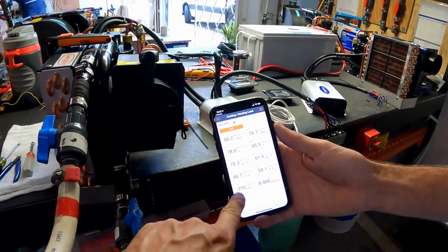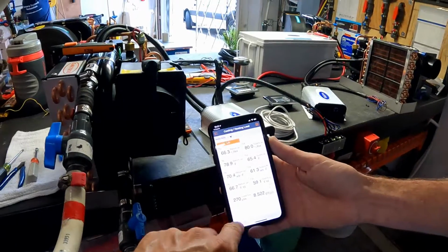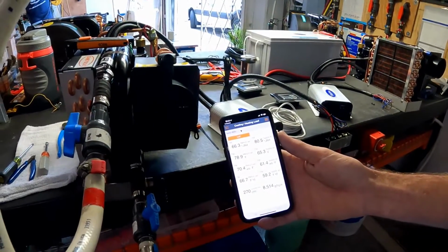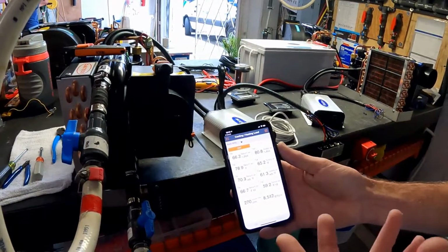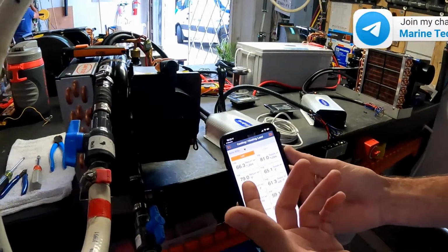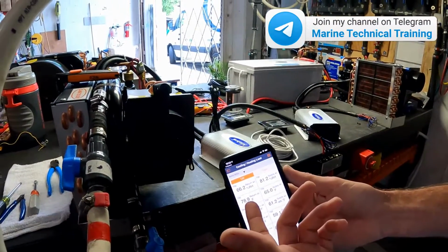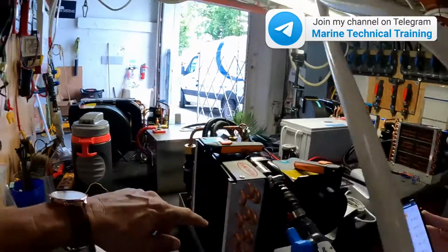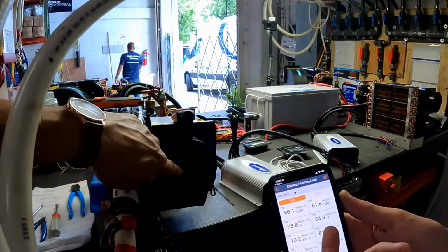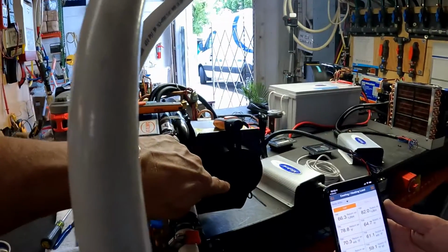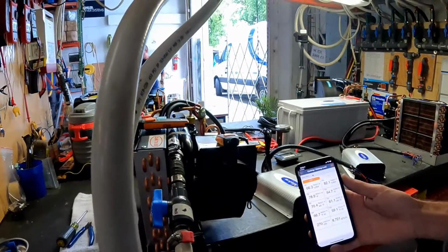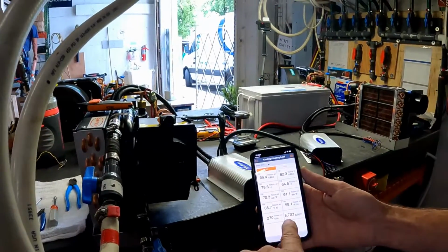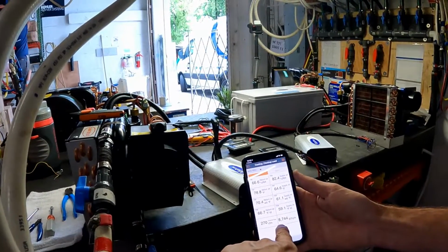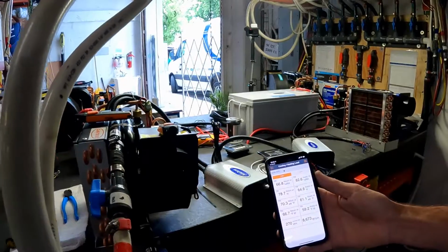That's correct, for 270 CFM according to the information from the anemometer. Here what we're looking at is a temperature in the return of 78.9, so we'll call it 79 degrees. This is the temperature at the return going into the unit, and then right here we're coming out with 64 degrees, 64.7.